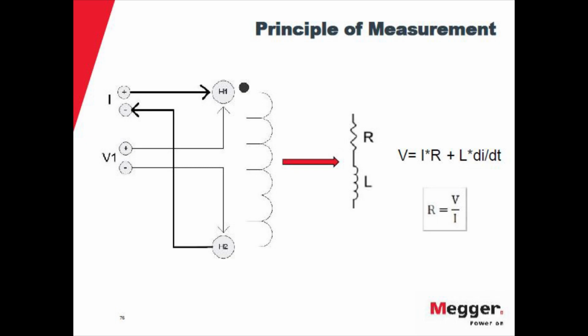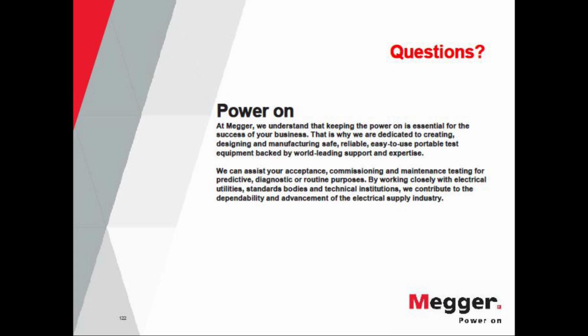And once you finish the test, by saturating or charging this energy, you are magnetizing the transformer. So you also need to perform a demagnetization procedure. The actual DLRO doesn't have that either. So this very specific instrument is called the MTO, Megger Transformer Ohmmeter, and it can demagnetize and it can handle the energy properly. I think I ran out of time, so...